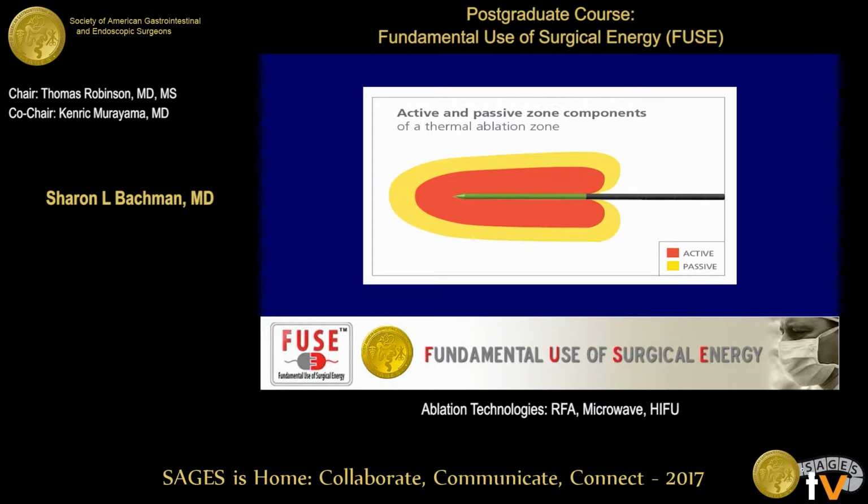So essentially, you have a long probe. This can be placed by open technique. It can be used laparoscopically. It can be used by interventional radiologists and cardiologists. So usually we use this in conjunction with some kind of imaging, whether it's intraoperative ultrasound, which is the most frequent.